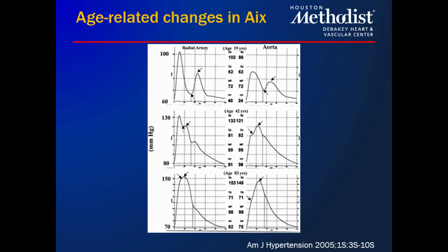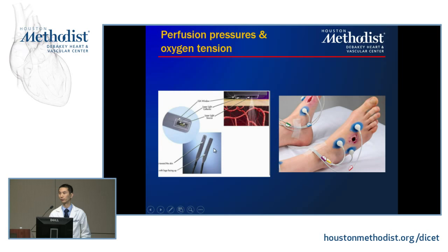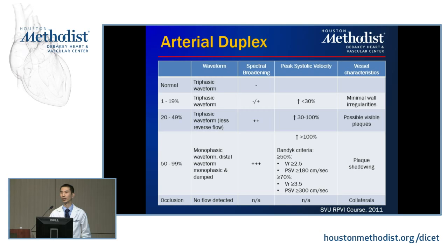Other tools in the vascular lab include laser Doppler for skin perfusion pressures, assessing signs of poor perfusion, and transcutaneous oxygen tension using silver-platinum electrodes that pick up oxygen coming off the skin. When stenosis needs to be confirmed, this is coupled with an arterial duplex, which has extensive criteria for grading.